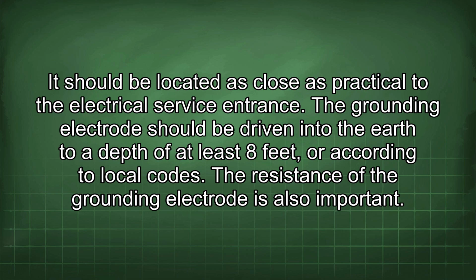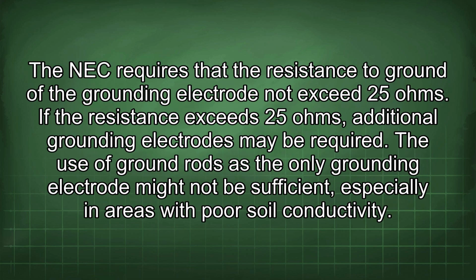The grounding electrode should be driven into the earth to a depth of at least 8 feet, or according to local codes. The resistance of the grounding electrode is also important. The NEC requires that the resistance to ground of the grounding electrode not exceed 25 ohms. If the resistance exceeds 25 ohms, additional grounding electrodes may be required.